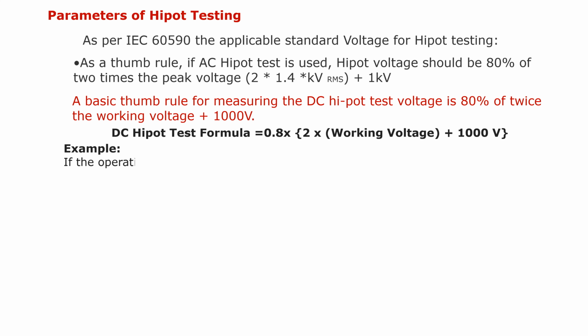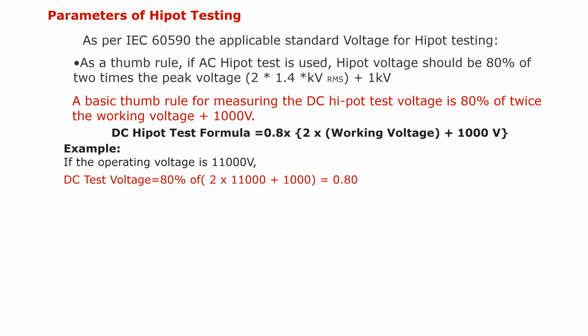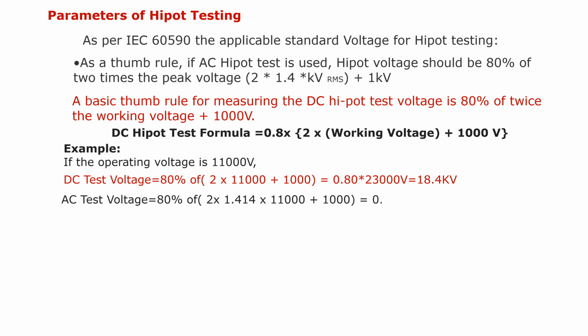Example, if operating voltage is 11,000 volt, DC test voltage is equal to 80% of (2 into 11,000 plus 1000), which is 0.8 into 23000, equal to 18.4 kV. AC test voltage will be 80% of (2 into 1.414 into 11,000 plus 1000), which is 0.8 into 32108 volt, equal to 25.7 kV.